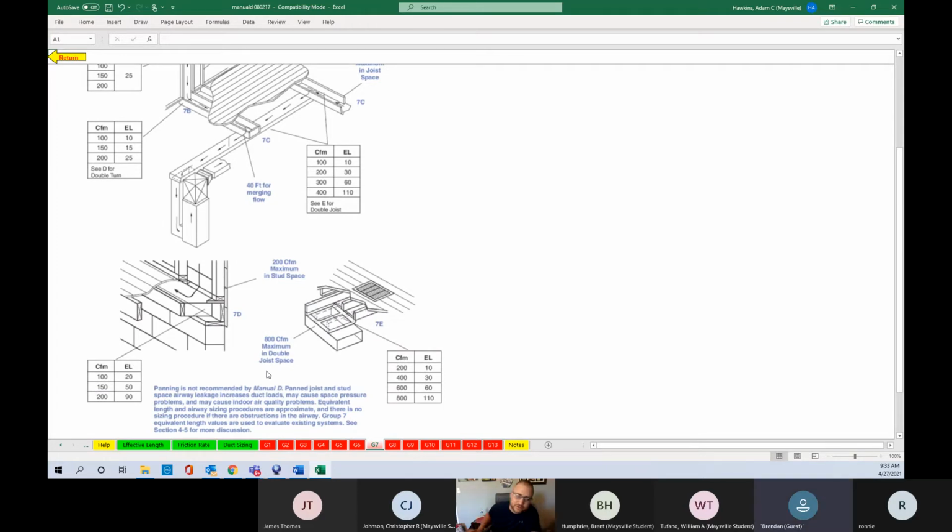So this was something Chris asked me the other day that he was watching online. He said, hey, I found out that people use floor joists and run their returns through the floor joist, and all they do is put some metal or something underneath of it, and they use that as a duct. You can do that. That's called panning a joist. You can do that on return. You can't do it on supply unless you insulate that supply or insulate that duct. It's like in dire straits, the only reason you do that. But return, it's done all the time.